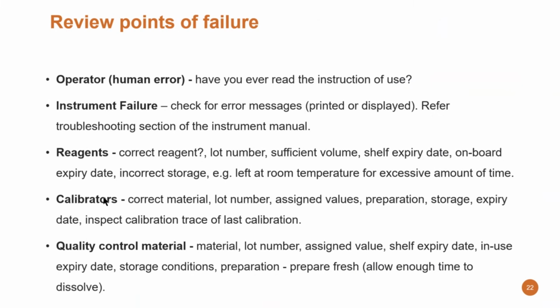So there might be an instrument failure. Check if there is an error message. This might be printed or displayed on the instrument. Refer to the troubleshooting section of the instrument manual to figure out what the reason for this error message could be. Reagents: have you used the correct reagent? Check the lot number. Is there sufficient volume of the reagent in the bottle? What about the shelf expiry date in the refrigerator and also on board? Or is there incorrect storage, for example, the reagent has been left at room temperature for quite a long time, which may have deteriorated the reagent?